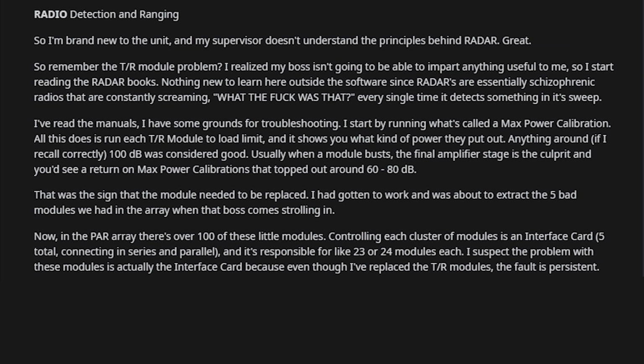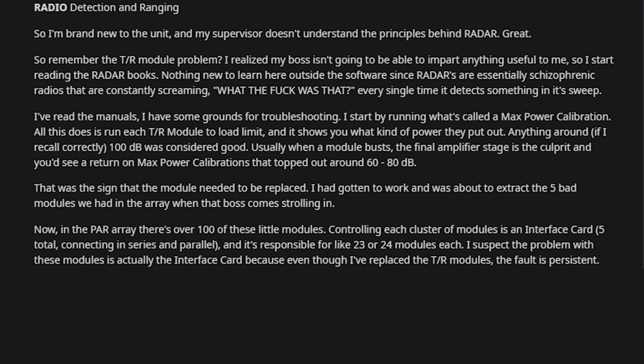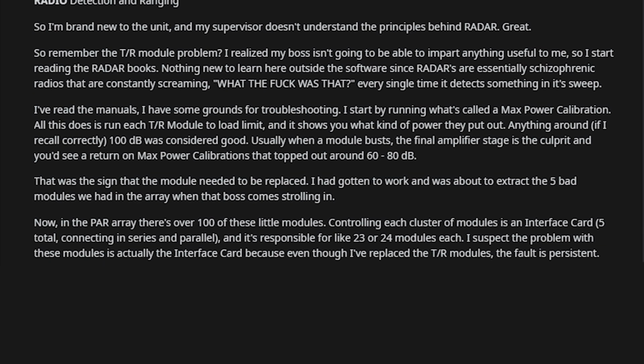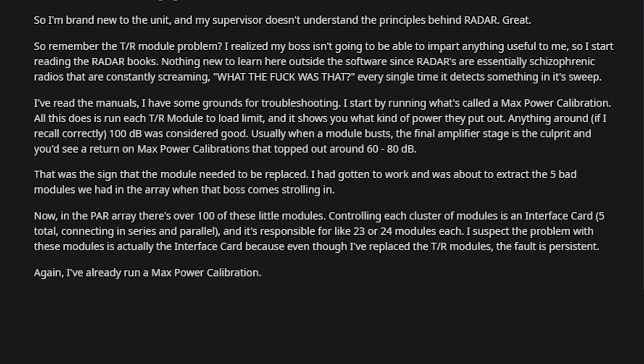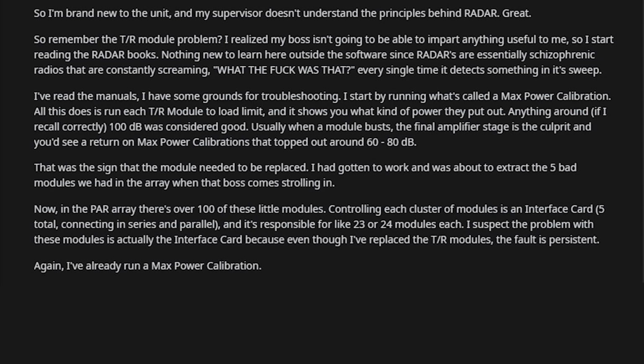I suspect the problem with these modules is actually the interface card, because even though I've replaced the TR modules, the fault is still persistent. Again, I've already run a max power calibration.